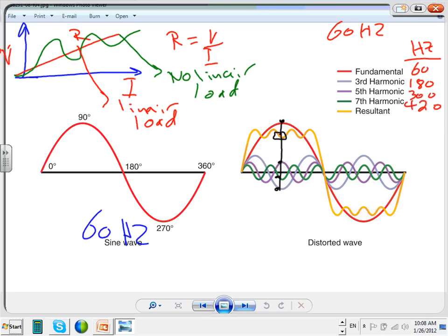This signal is ugly in terms of the effect on the electrical equipment. It heats conductors. It creates more heat. It creates more nuisance tripping because of that heat. On the neutral, it makes electronic equipment malfunction. It creates a whole lot of issues. That's where harmonic becomes a big deal.